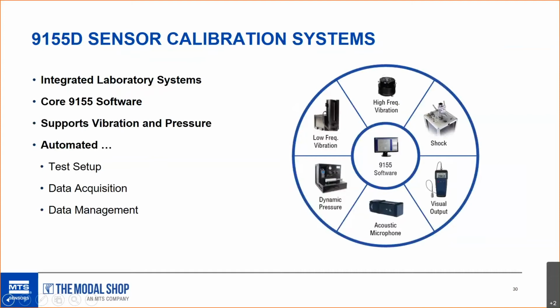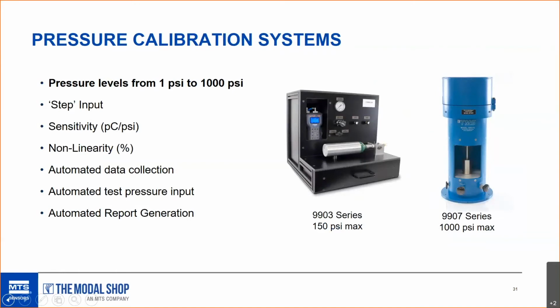And the next one we'll talk about here is the dynamic pressure option, which reproduces the factory technique used on these combustion dynamic sensors. The 9155 software ties everything together by automating the test setup, the data acquisition, and the data management. So it's another level of complexity and another level of automation, tying the whole system together. It's interesting, these pressure cal systems for combustion dynamic sensors, we can calibrate them with two different calibrators. They have different max pressures and they overlap.